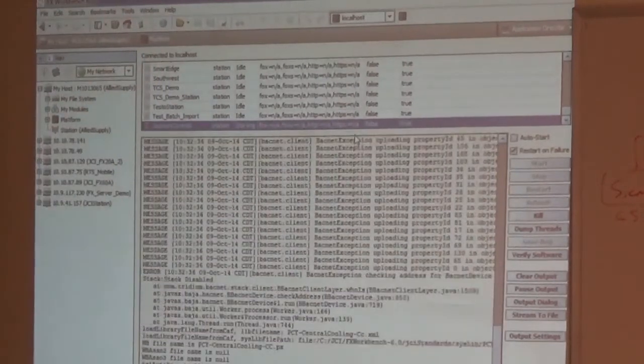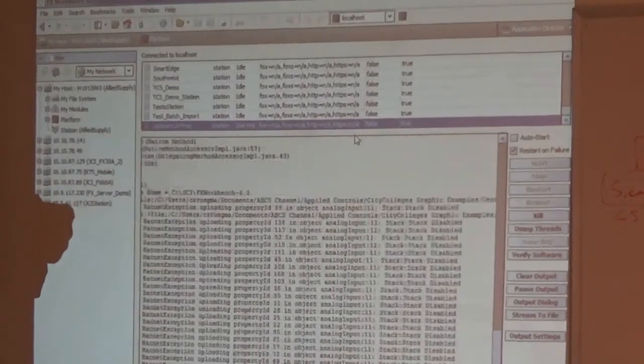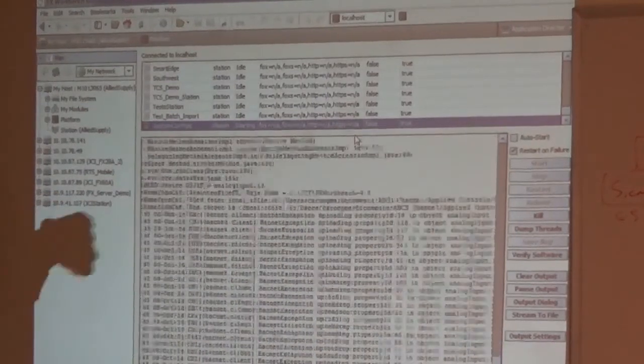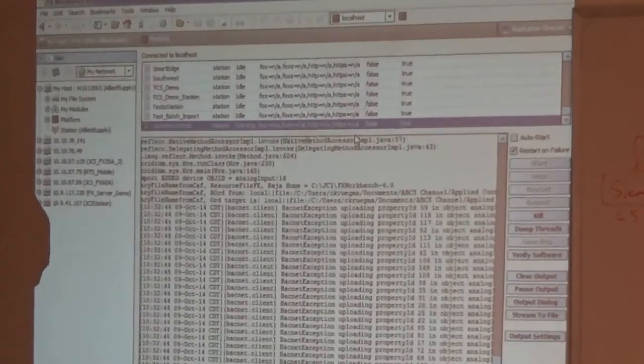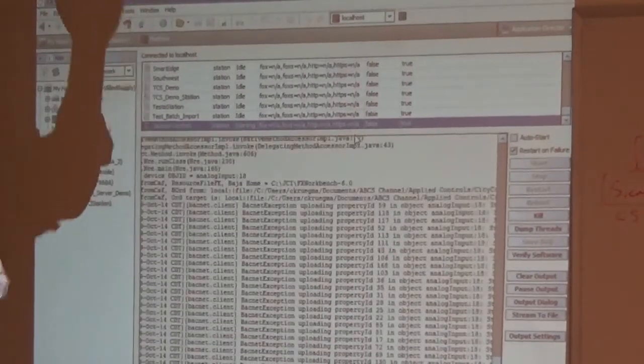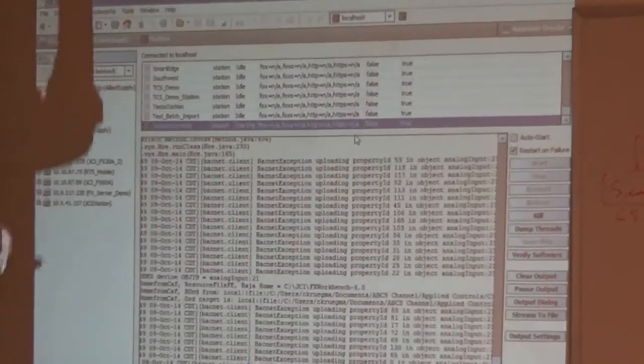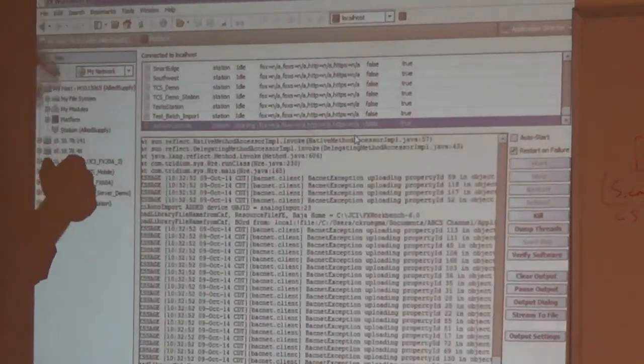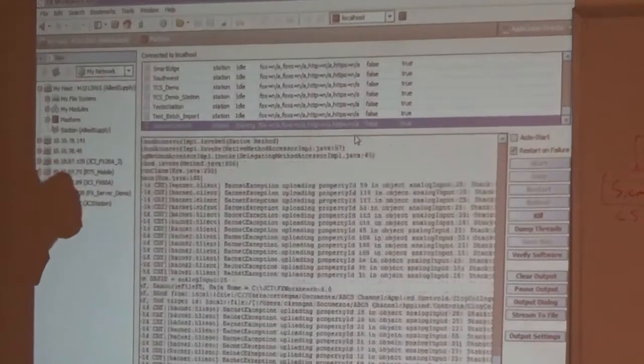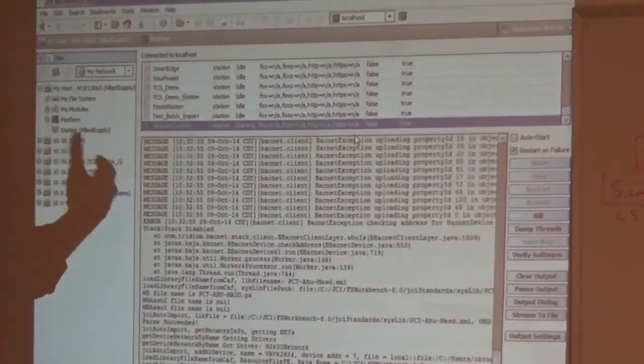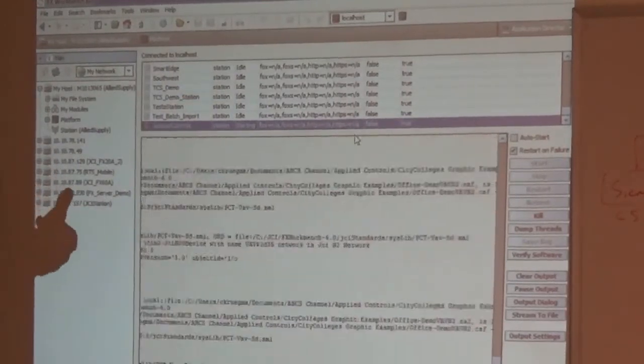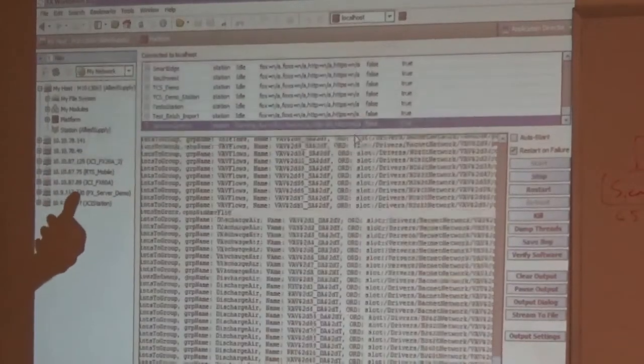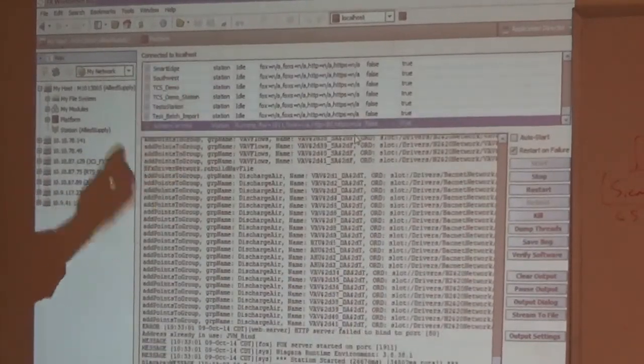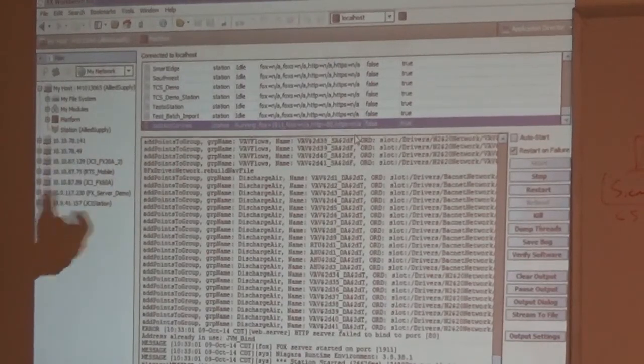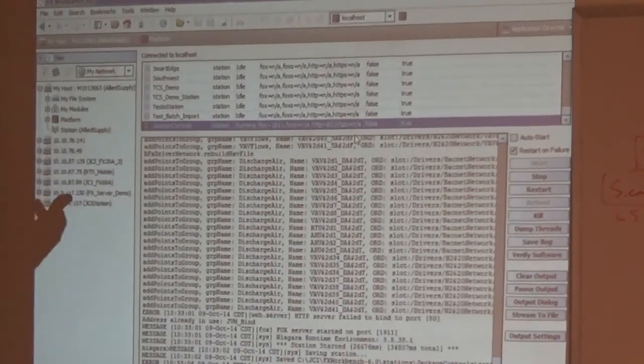Well, what we do is when you use our appliance, let's say you go to a network and add a device. When you find a device that we have, we've got system library files that say, if you have an AE2 application, here's the subset of all the possible points that come in when you discover it, and we'll automatically put trends, alarms, or totalizations on these points. If you like more points, you can change the system library around and say, I always want box heating temperature, right? We don't bring that one in as normal, but you can, or K factor. I always want to see what the K factor is, right? We don't bring that one in, but if you want to, you can automatically have that come in.